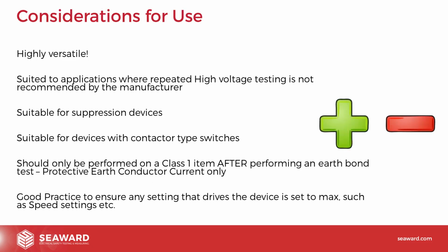So it is a highly versatile test. Essentially, we're only performing the test at normal operating voltage, so it's suitable for any of our 110 240 volt products. It's particularly suited to applications where the manufacturer does not recommend repeated high voltage testing, which could cause wear and tear in the device and ultimately make it less safe.